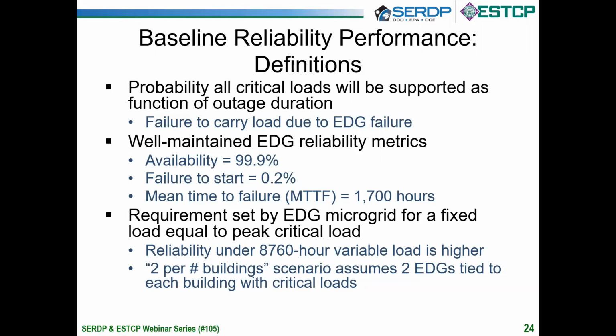Failure to start has been shown to be a fraction of a percent for well-maintained generators. I will tell you that when you have poorly maintained generators, it is multiple percents and quite different. But we're assuming that generators are maintained properly, which means that they're maintained in accordance with the UFC criteria. The final characteristic is the mean time to failure, which we've estimated to be 1,700 hours. Poorly maintained generators can fail within a day or two on average, but well-maintained generators will last this long. But if you're looking at multiple generators for a week-long outage, you have to expect a certain number of failures. So this is what defines the performance of individual generators, which constitute the system of generators in a microgrid.